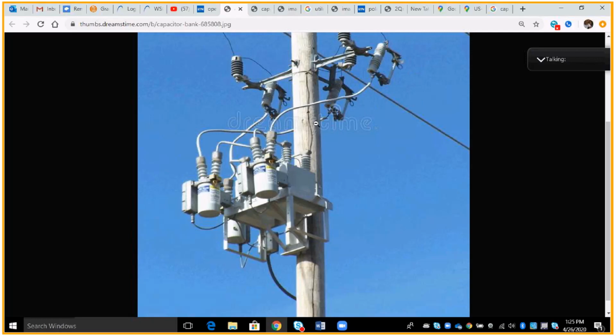All right. Now that I have this situation, do I have a visual open point? Switch open, switch open, switch open. Yes, you do. Now you're able to start work here.